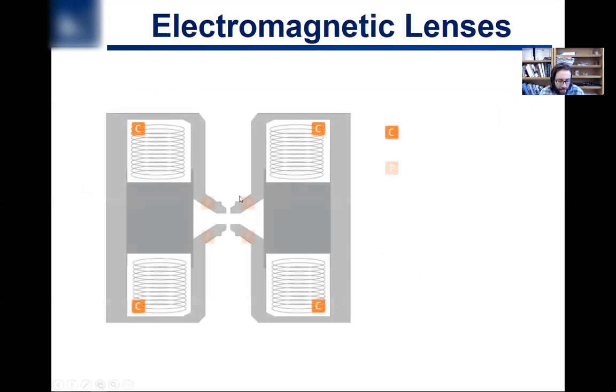And then you have these electromagnetic lenses. You don't have glass lenses, you have coils. And so it looks something like this: electron beams going through these different poles of electromagnets, and then these are the coils. And you're able to control the strength and the direction of how this lens bends the electron beam by playing with the current voltage that goes through these coils.